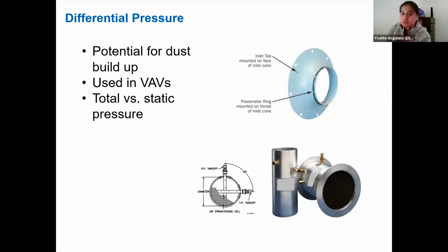In terms of the piezometer ring, it's using the Venturi principle to measure airflow rate. There's a sensor located at the outer edge of the ring, measuring the pressure at that outer edge. And then there's an additional sensor at the inner ring, also measuring pressure. The difference between those two pressures, combined with the Venturi equation, which I don't have written here because we don't have to do the math, the device does it for us, calculates the airflow going through this device.